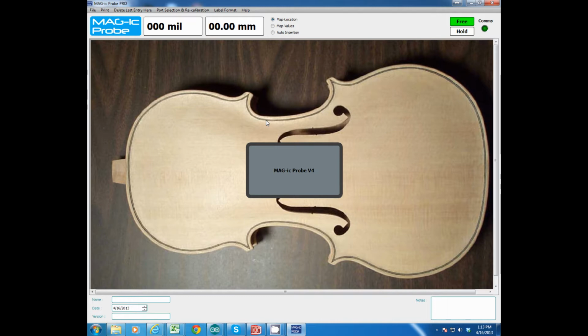So I'm going to go through the calibration procedure. It tells me to attach the ball. I attach the ball onto the probe, and the next step is to remove the ball. That's the calibration procedure, and it should say calibration succeeded and that it has detected the big ball. Okay, so the probe is now ready to measure. In the top right-hand corner you'll see that the green light is now flashing, and when I move the ball on the probe we have some changing readings on the screen itself.